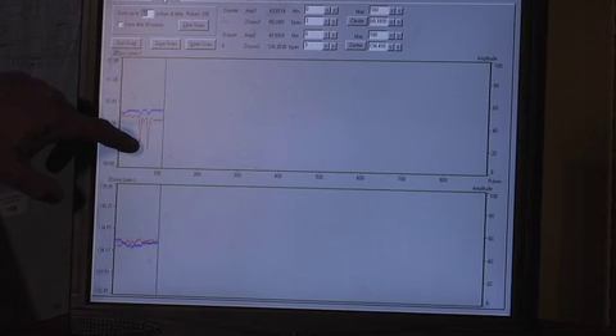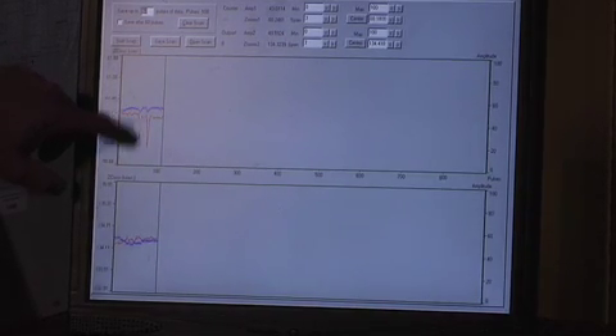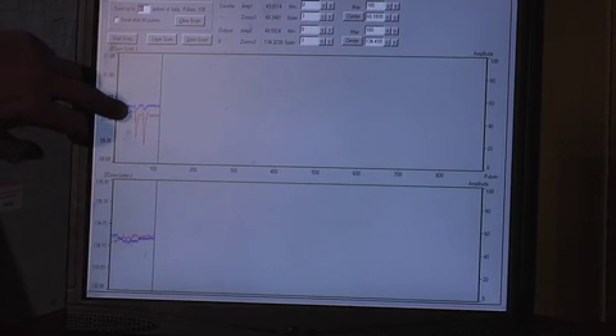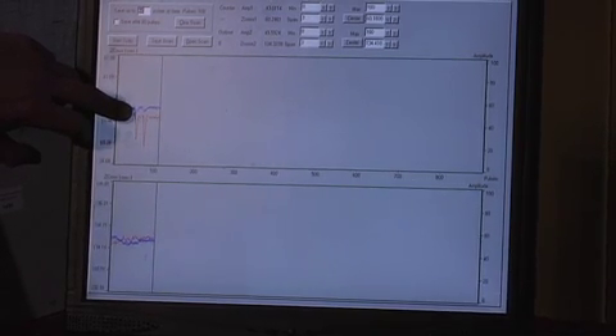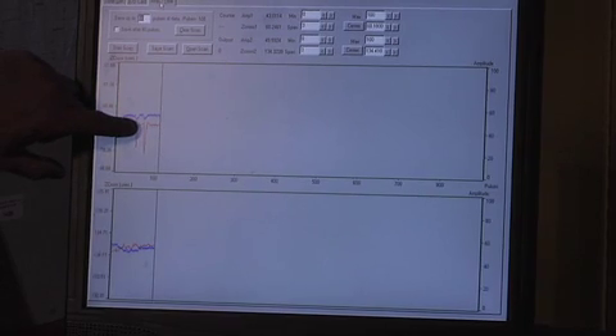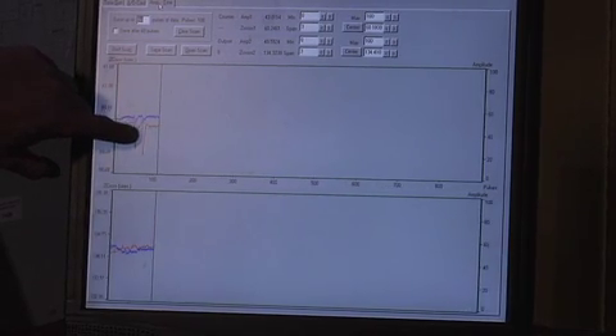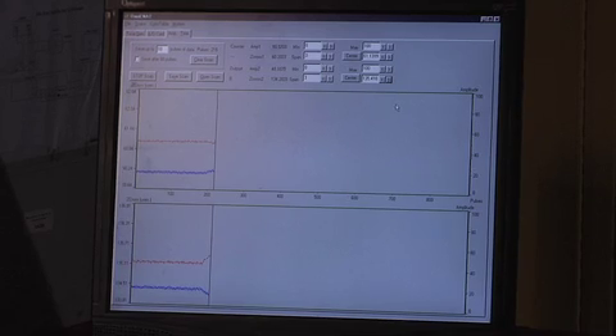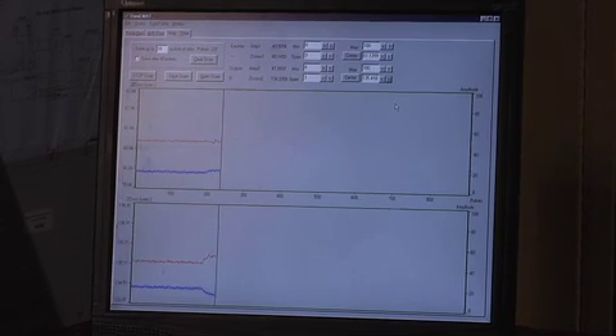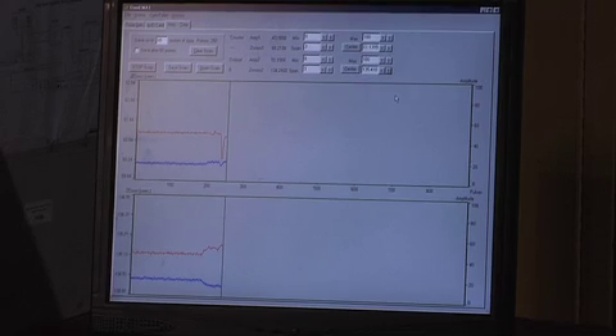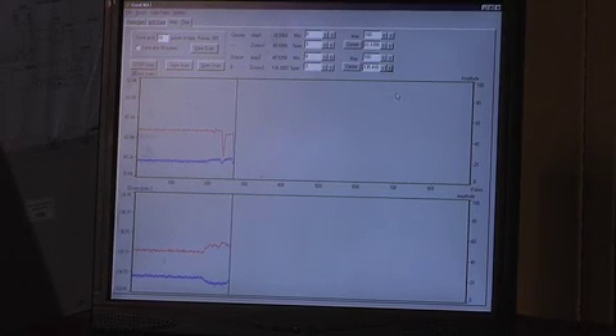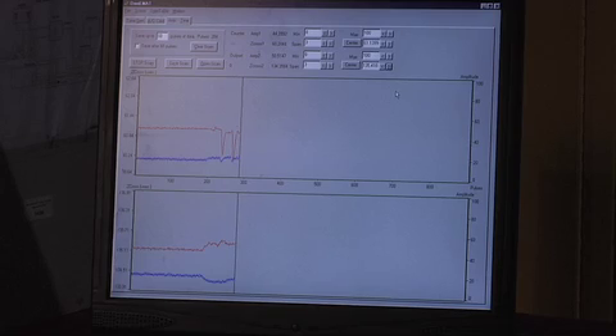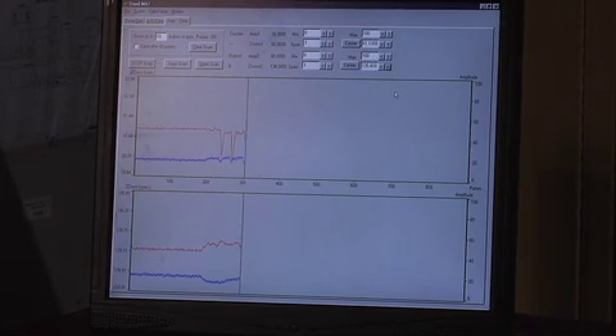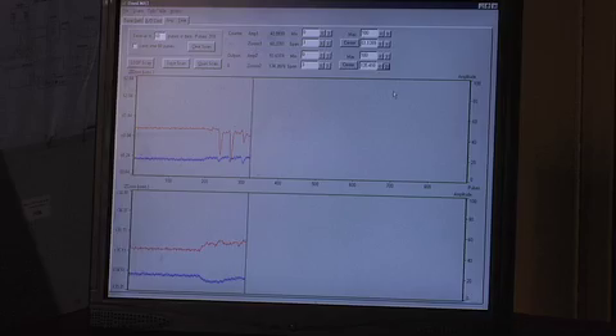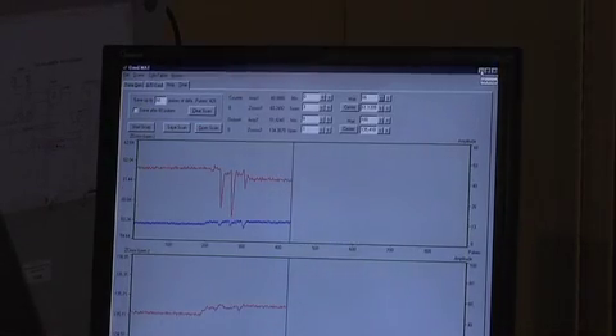Another form of the software is the real-time collection mode. Your red line represents your amplitude. Your blue line represents the time of flight, the time it takes for this sound path to travel from your transmit to your receiver. This is what is saved and collected. As you scan your defect, your 50%, you'll get a drop in amplitude, but you also get a drop in your time of flight. As you scan over your 75% defect, you get a drop in amplitude as well, much larger than your 50%. We can save this data image and reopen it again in an algorithm mode.